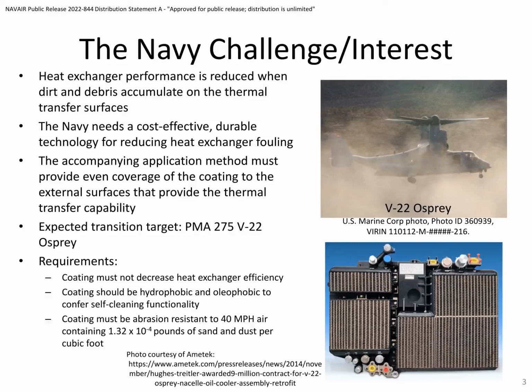The coating needs to satisfy a number of requirements. The most critical is that the coating itself cannot decrease the heat exchanger efficiency. The coating must also be hydrophobic and oleophobic, so that it confers the desired self-cleaning functionality. The coating must also be abrasion resistant, so that it can operate in these dusty environments. The specific heat exchanger shown here, called the nacelle oil cooler assembly, is specified for an air intake velocity of 40 miles per hour, with a given concentration of sand and dust per cubic foot.